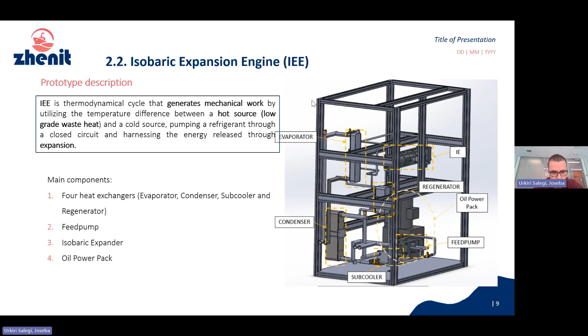As you can see, the green lines are the refrigerant circuit, and the yellow lines are the hydraulic module, which is the circuit responsible for giving us the work output, or the hydraulic power in this case. Starting with the feed pump, instead of having an electrical pump to move the refrigerant, we use a cylinder piston system that is moved by an oil power pack, which is a hydraulic pump. This hydraulic pump moves the oil that is responsible for moving two single-acting pistons on the same shaft, and in the middle of this shaft they share a double-acting piston that is responsible for pumping and increasing the pressure of the refrigerant.